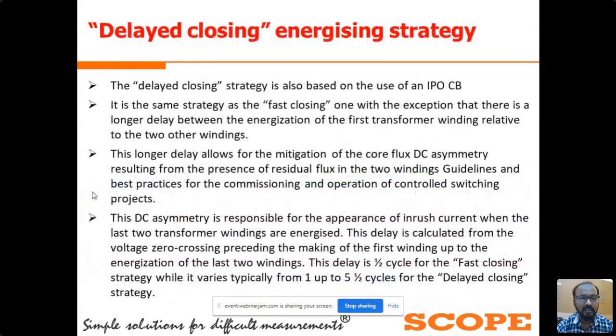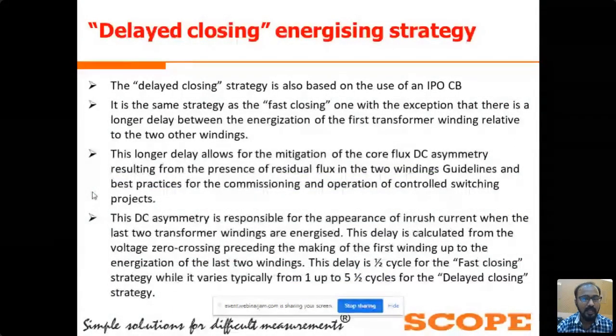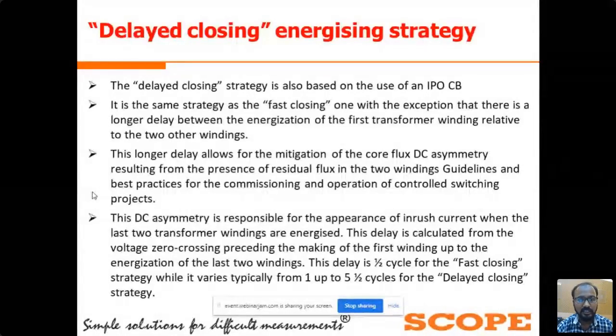Another method that we are using is the delayed closing energizing strategy. The delayed closing strategy is also based on the use of an individual pole operated circuit breaker. It is the same strategy as the fast closing one. The only difference is that we give a delay between the R phase operation and the Y and B phase operation.